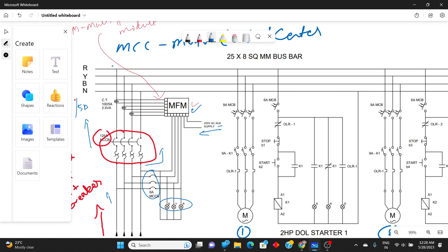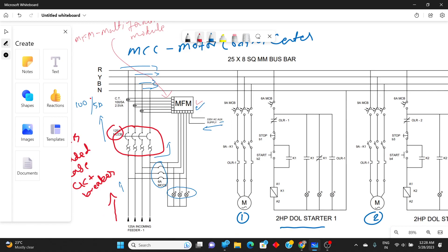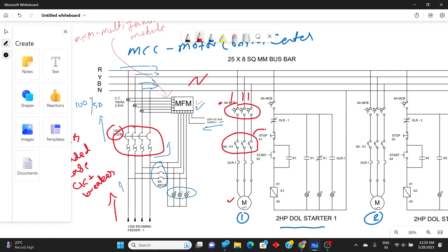From the auxiliary supply we have taken three phase, and from this our circuit is starting. Three phase is taken and given to an MCB. If any fault occurs at this side, this circuit breaker will trip. A 9 ampere MCB is sufficient for this motor circuit.